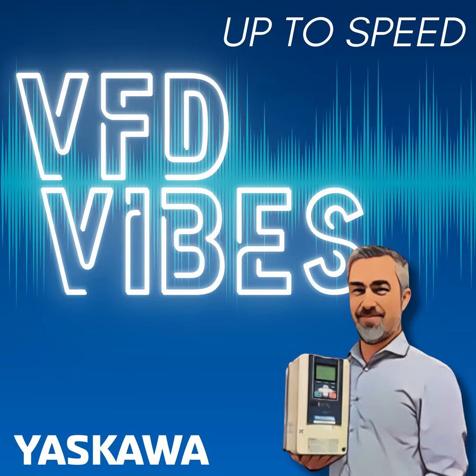Now I convinced him that the problem was outside of our drive, and he's got to figure out why his signal's not there. Nice work. So it's important to remember that we need both a run command and a speed reference, because if we don't have either of those, then our motor is not going to turn.